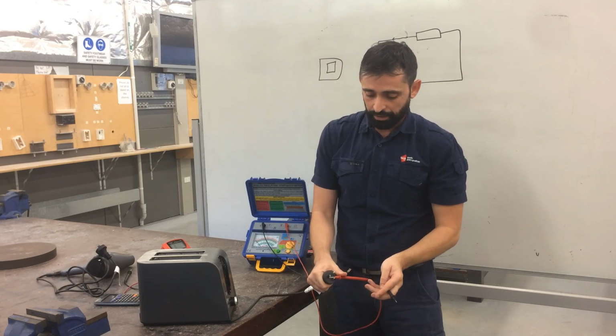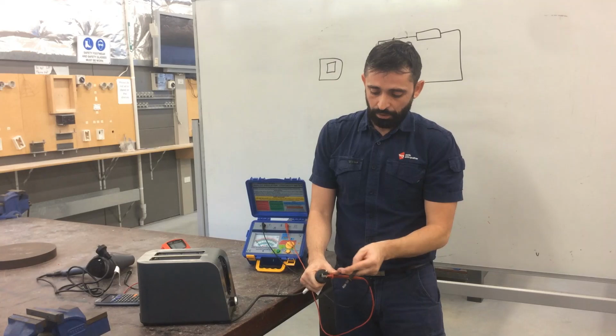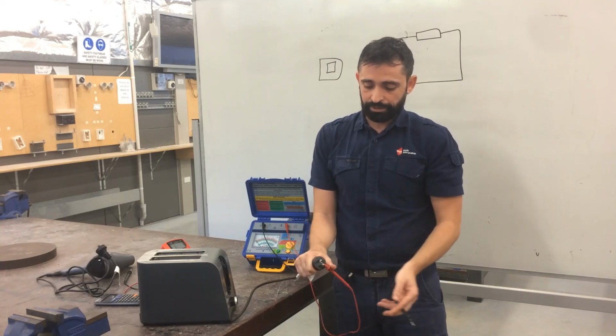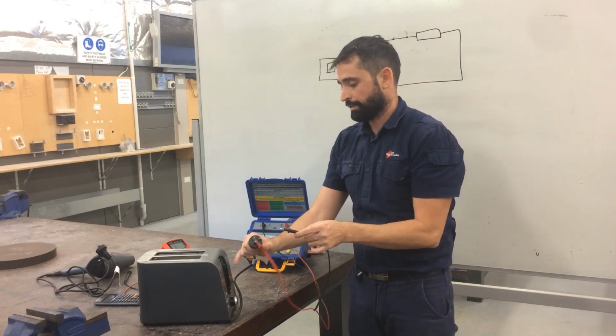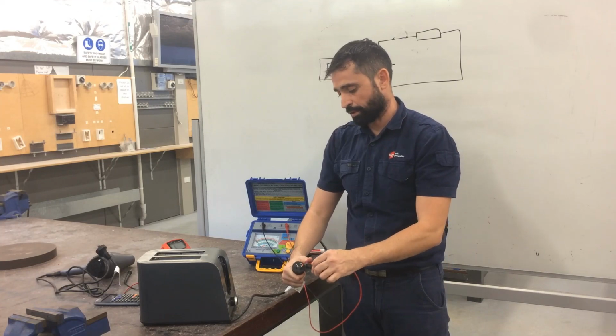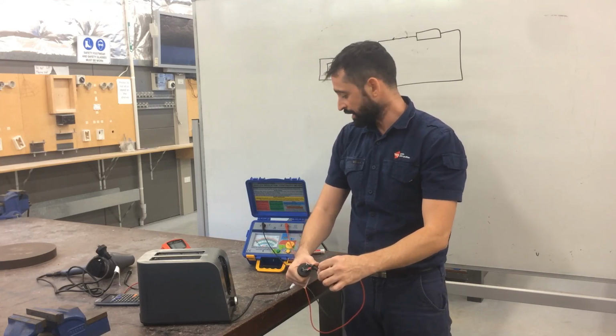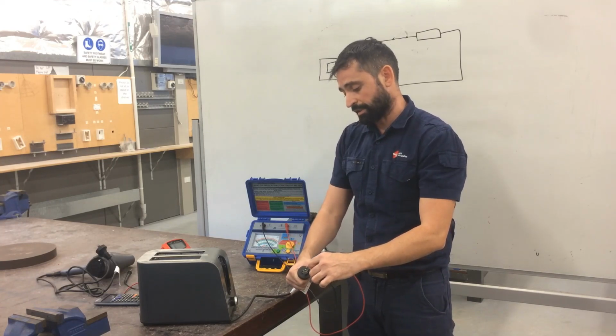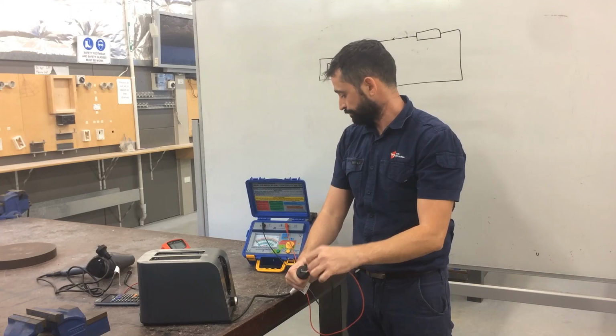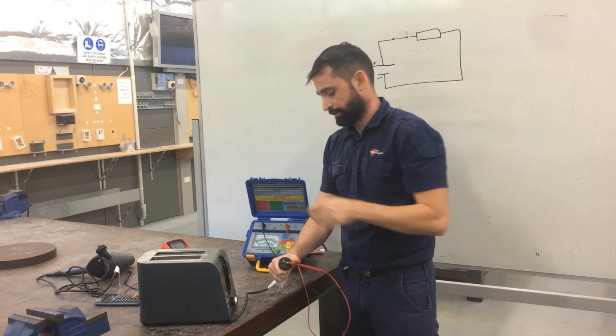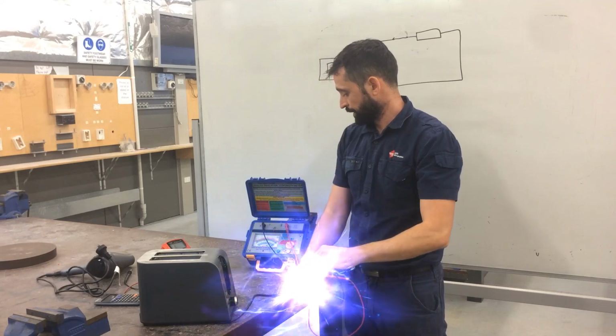So what I do is I cross the probe, the active probe, across neutral and active like that, so I can use one hand. And then we can also get the other probe and touch it against the active probe just to see if the insulation resistance tester is going to show us a faulty reading. First we'll turn it on. Here we go. That says the faulty reading. That's what we don't want.